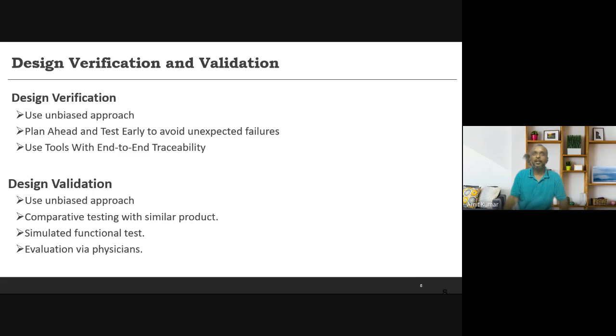Another important aspect is plan ahead, test early to avoid unexpected failure. The typical timeline for performing a validation from development could range from months to years. So the development, let's say, started. Typically, a ventilator would take around a couple of years in the development phase only. And the verification and validation are performed after that. So if we see an unexpected failure during design verification and validation, it will take a tremendous amount of time and resources, which is money, to fix it. So do it early so that your verification is easy to do and you don't see a major hiccup.